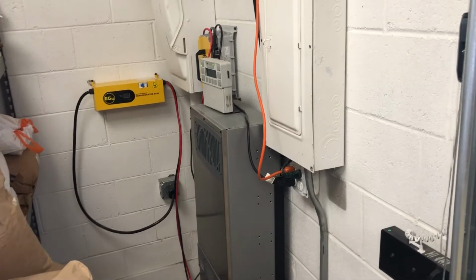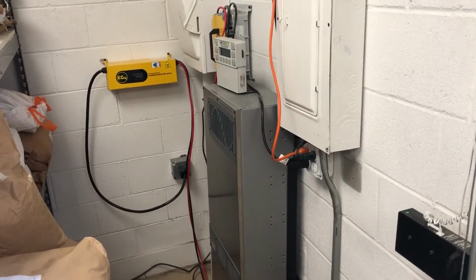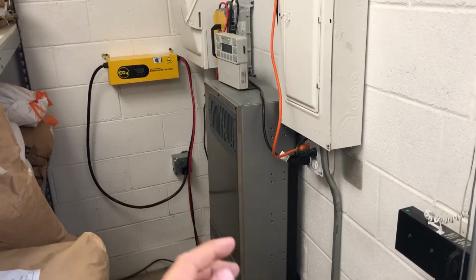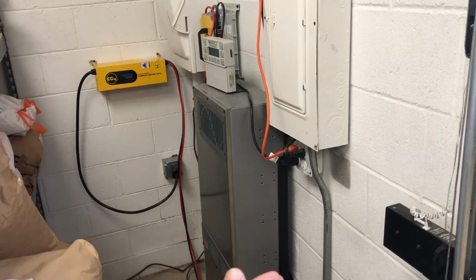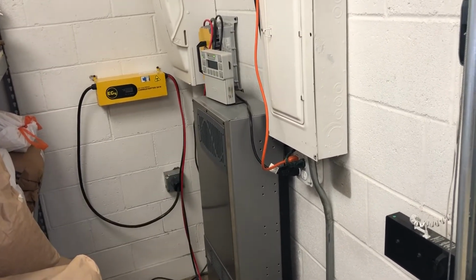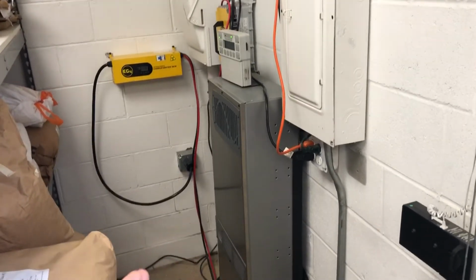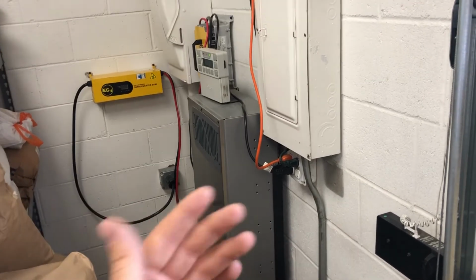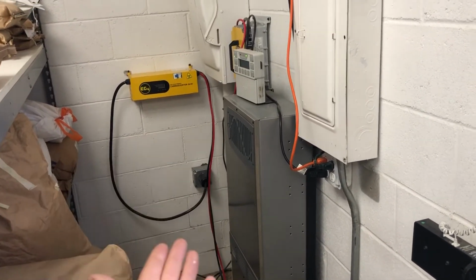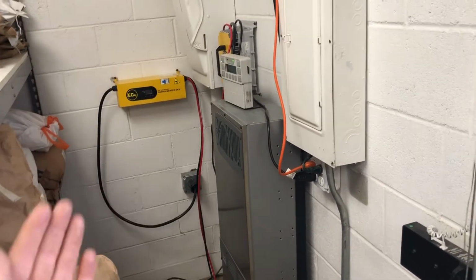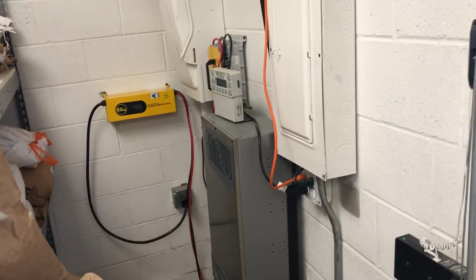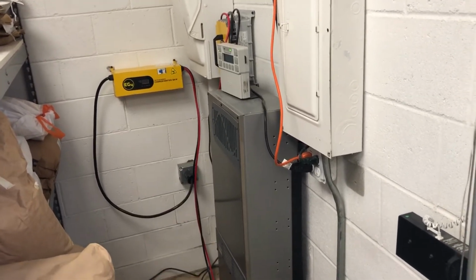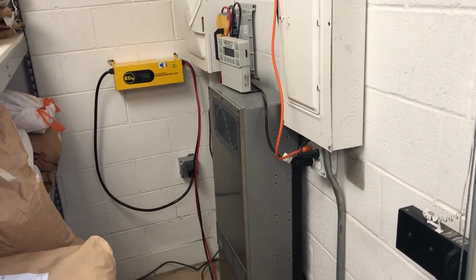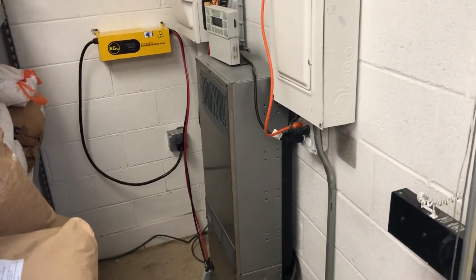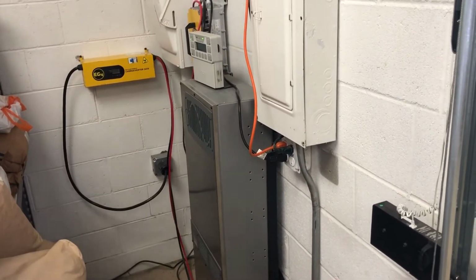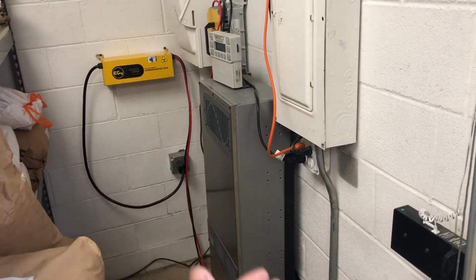But my experience with it is, and I spent a couple of hours on the phone with Outback, every single time you give the inverter an AC connection, it immediately drops the inverter and starts the charger and transfers all of the loads to the AC connection. And so what ends up happening is even though you have a 10 amp maximum on its AC connection, it runs it up to say 25 amps and then throws in an error code and says, you're over current on your AC connection. And I'm like, of course I'm over current on my AC connection. Why did you shut down the inverter? And basically the system can only be an inverter or a charger, but it can't seamlessly switch between the two.